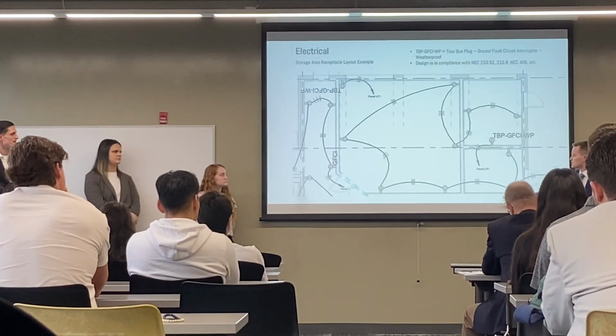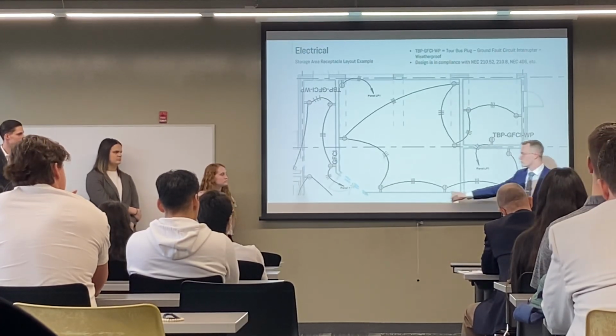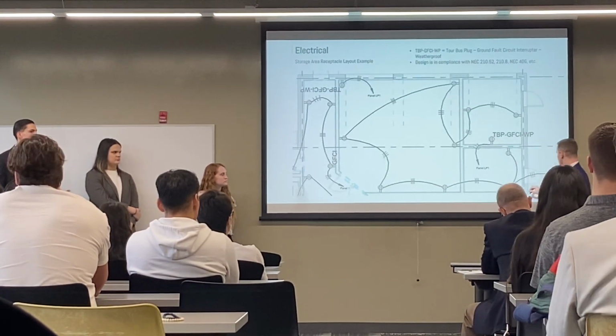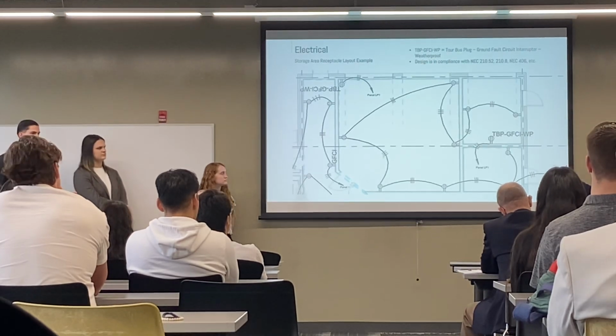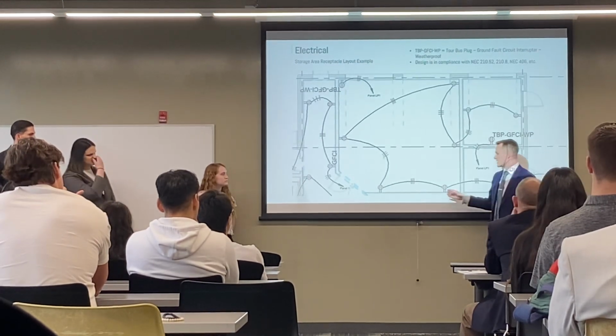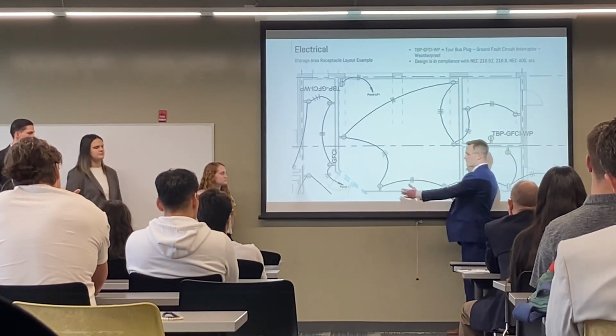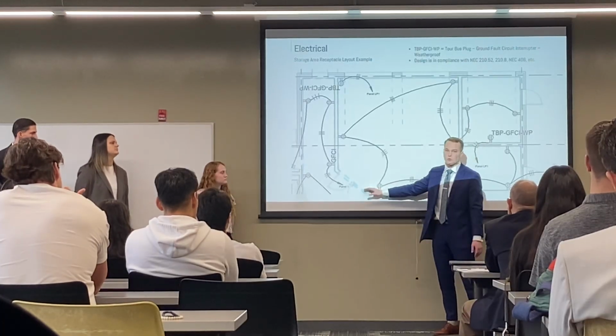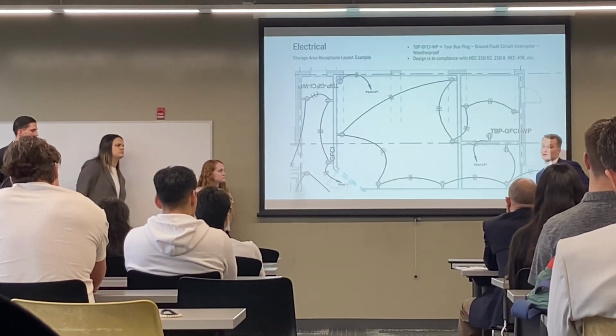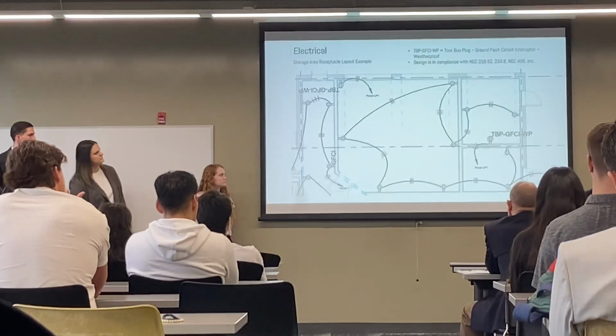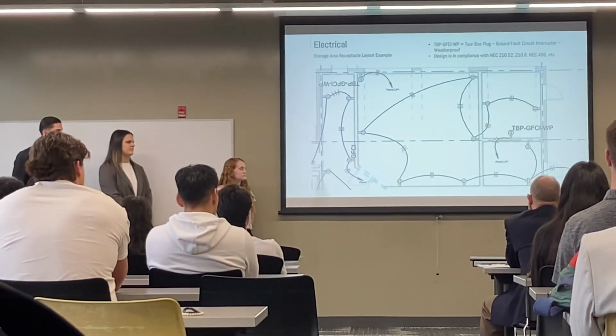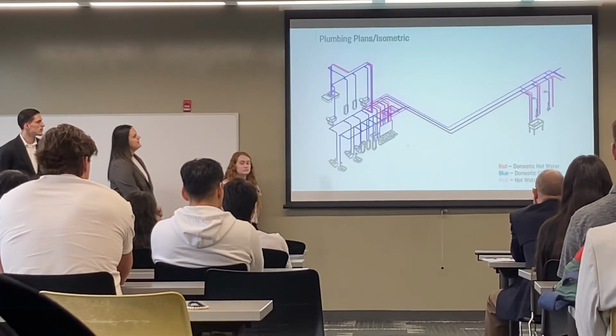Then here you just see some general receptacles, which are 120 volt duplex receptacles, and their home run is to panel 1 because it's on the first floor. They are spaced 6 feet between every receptacle, so 12 feet between 2, and 6 feet of every doorway, and all that comes from the National Electric Code. So it's in compliance with NEC 210.52, 210.8, 406, et cetera.